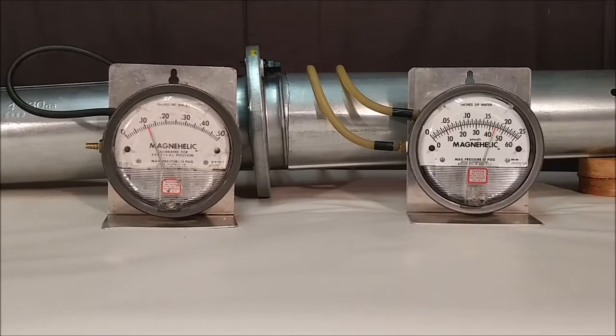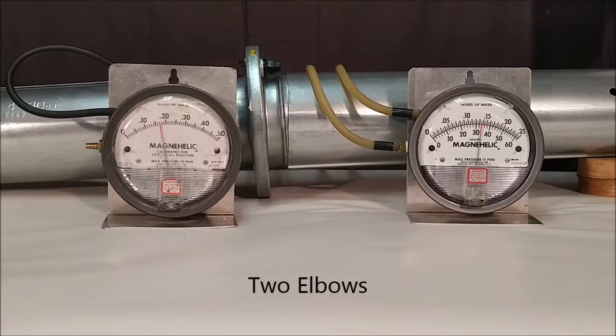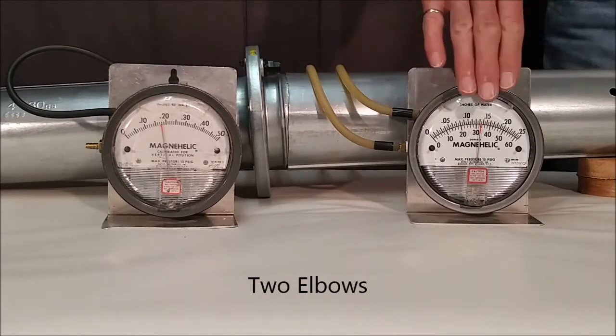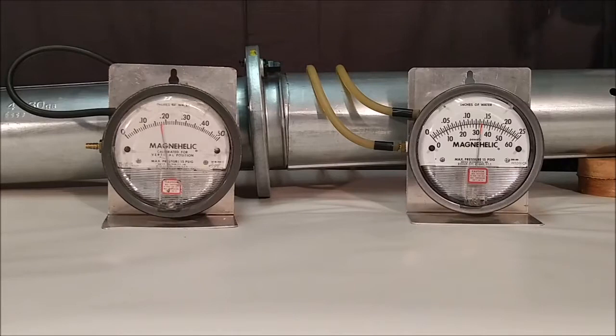Our starting point for this demonstration is the fan running in a near open condition with only a short bit of resistance incurred by the duct and the turbulence from measurement. Our first step is to introduce two elbows. We can see that the static pressure goes up and the flow goes down. Not too serious, but it's definitely measurable. And each of these 6 steps, they're all additive effects, that each one diminishes flow and increases the static pressure.